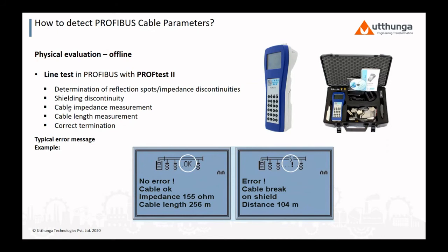The main measurements you take from the cable tester are line impedance and line length. If you go to the steel industry, cement industry, or where critical systems are, you don't know the cable length, and you cannot measure it, because the cables run everywhere. Sometimes it's a 100-meter cable, sometimes it's a 1-kilometer cable.